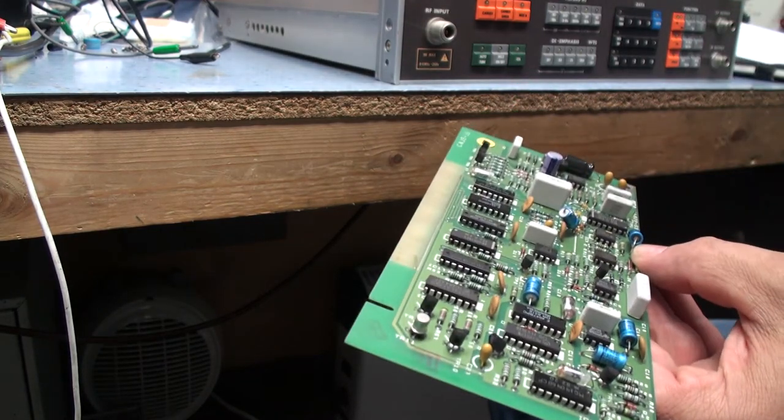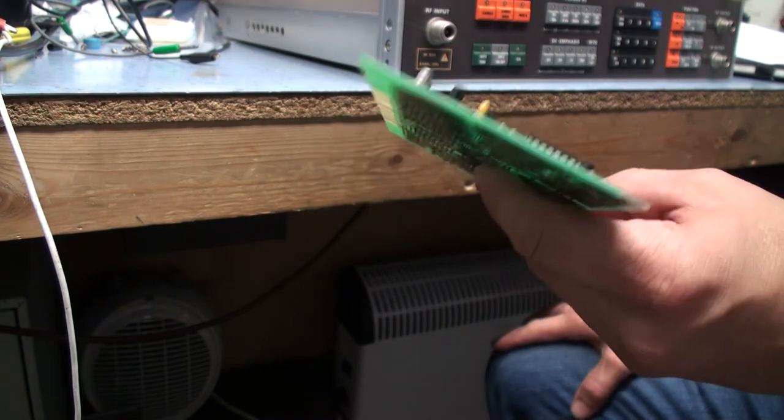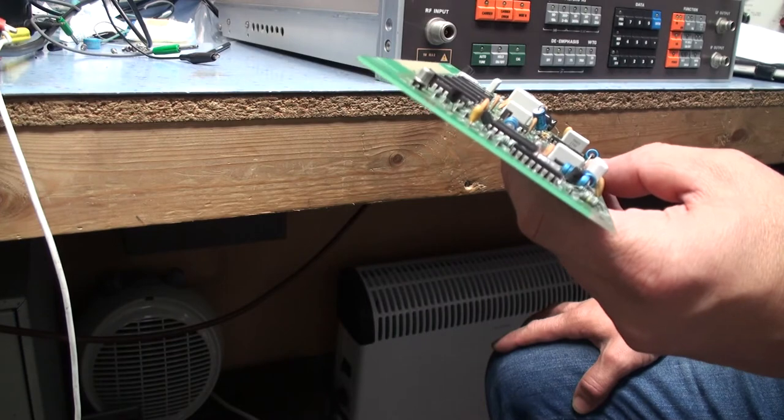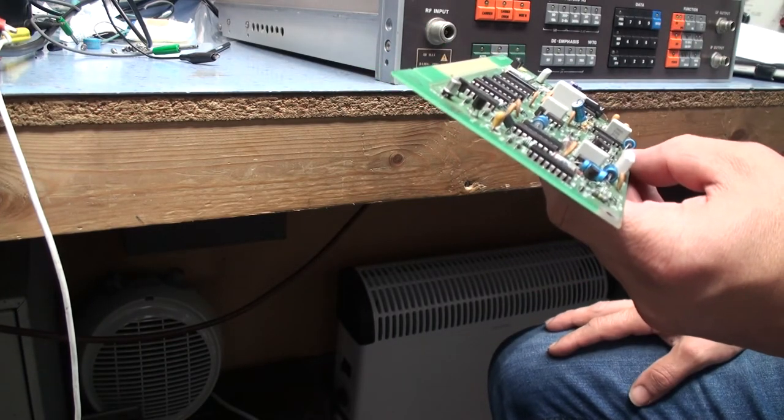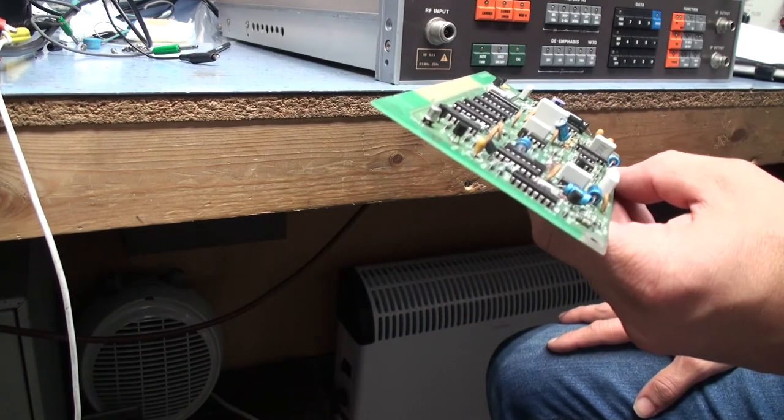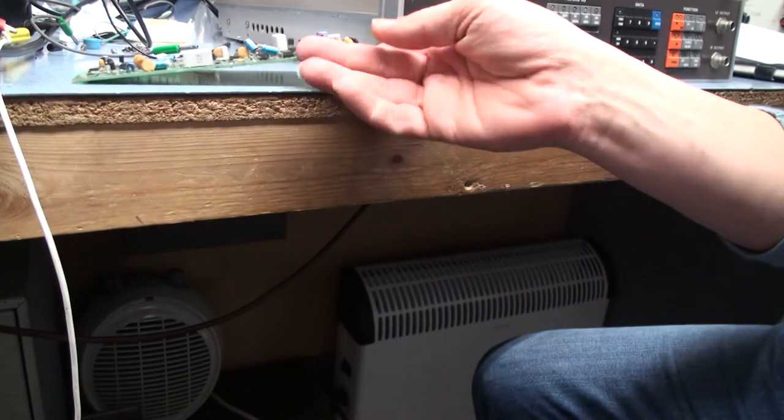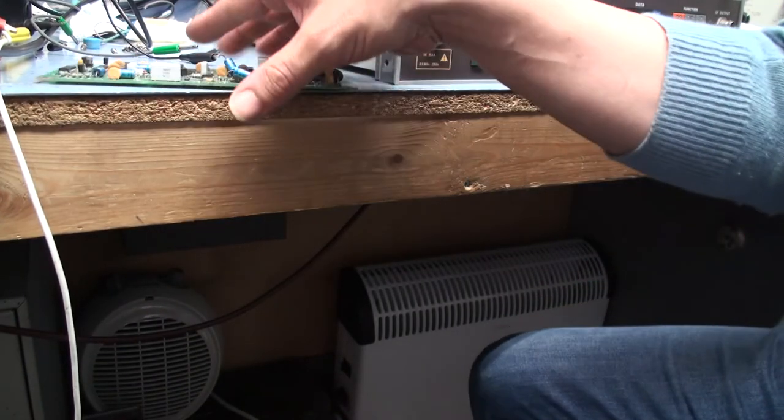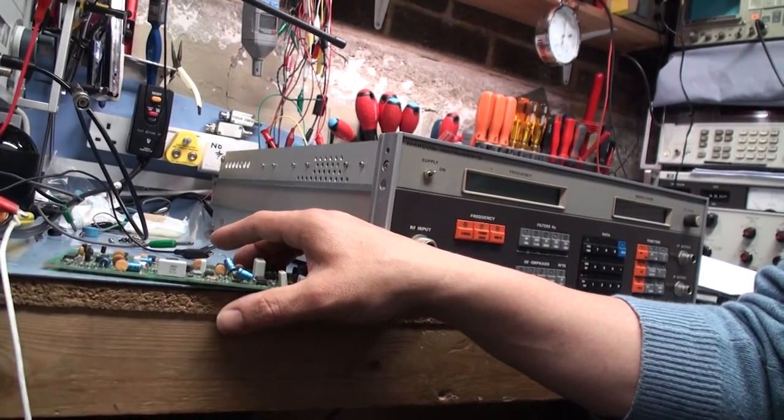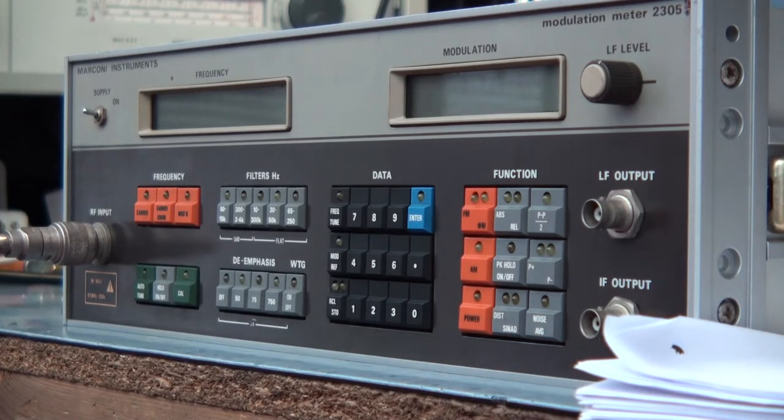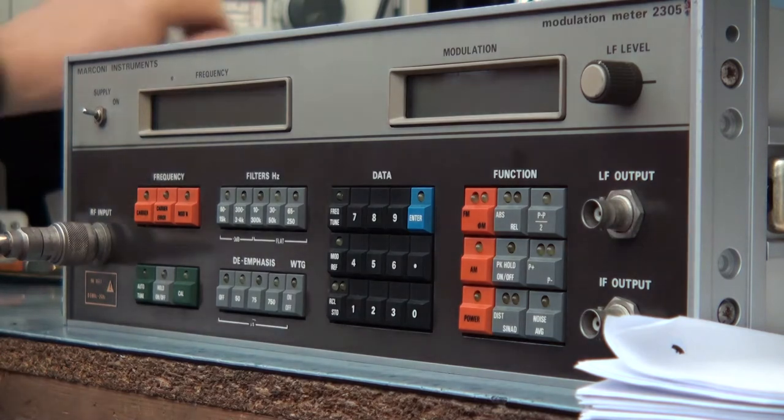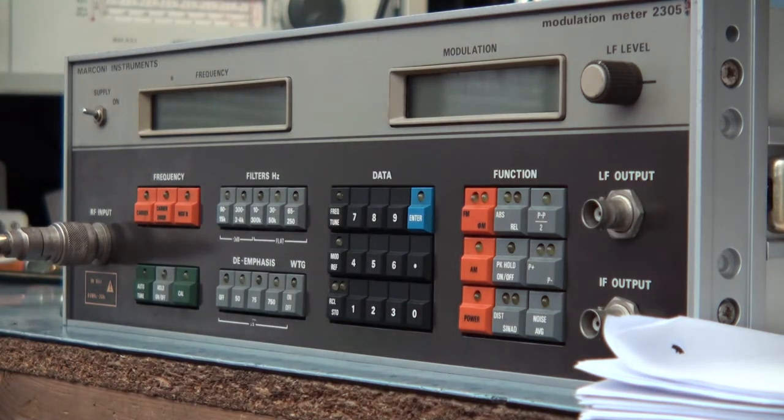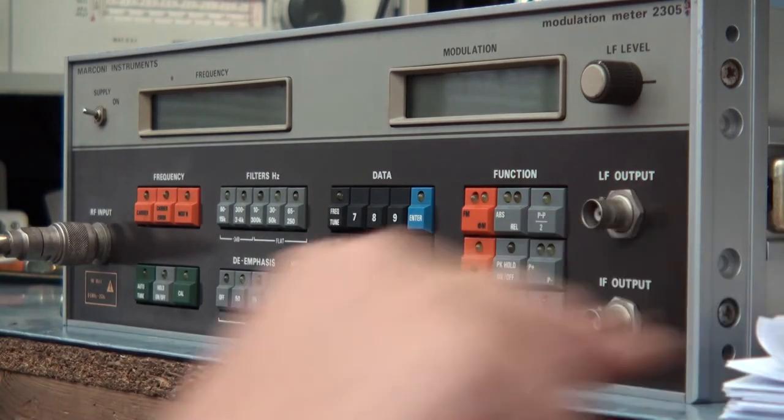Going through the paperwork and manuals, one thing I've ascertained is the reason why the thing stops working after a while is the internal oscillator which is an oven control crystal oscillator stops generating. That's quite a common problem with these internal oscillators on these Marconi instruments. Same with my Marconi 2019, it's a known problem that the oscillators aren't that great and are prone to just stalling.